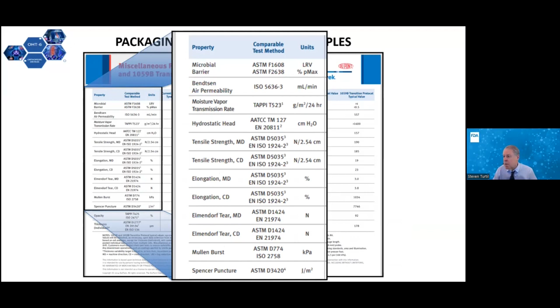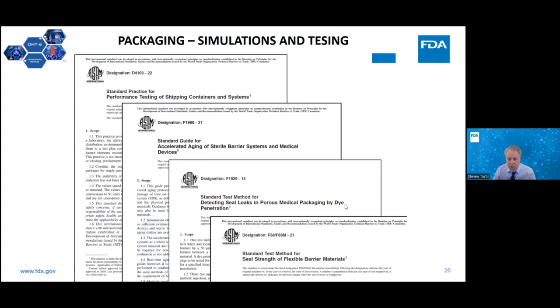So these are the ASTM standards. Again, these are the ones that I have listed in there. They're very commonly cited and used. The first two are for simulation, ASTM D4169. That's simulation, and the second one is for accelerated aging. And these are the test methods for afterwards: dye penetration and seal strength. And you can see how they would fit into here for stability, and you can see how they fit in here for package performance testing.